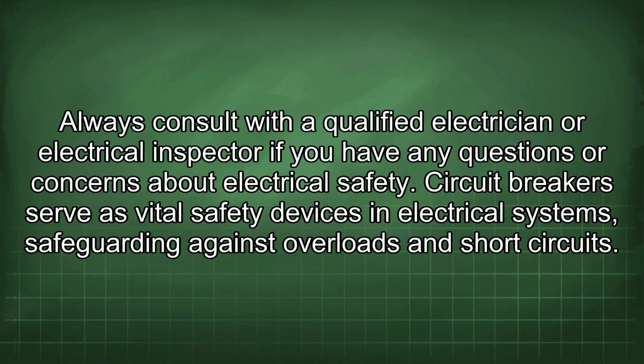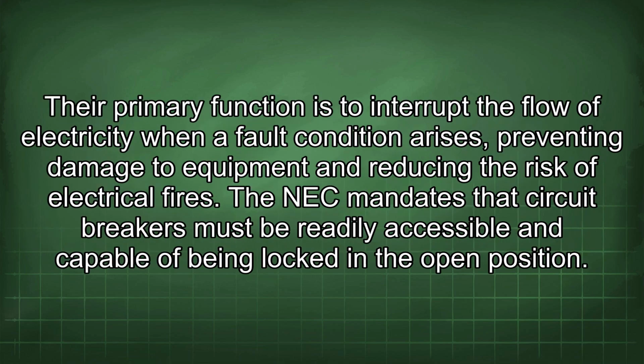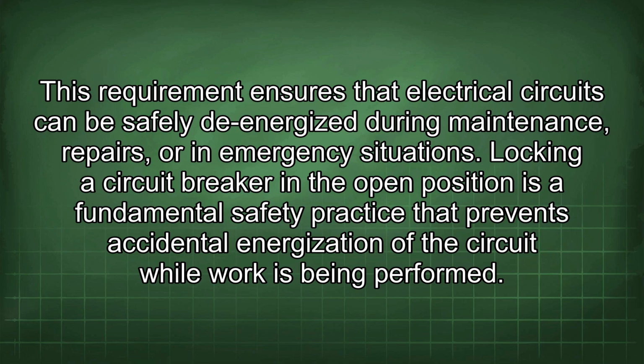Circuit breakers serve as vital safety devices in electrical systems, safeguarding against overloads and short circuits. Their primary function is to interrupt the flow of electricity when a fault condition arises, preventing damage to equipment and reducing the risk of electrical fires. The NEC mandates that circuit breakers must be readily accessible and capable of being locked in the open position. This requirement ensures that electrical circuits can be safely de-energized during maintenance, repairs, or in emergency situations.